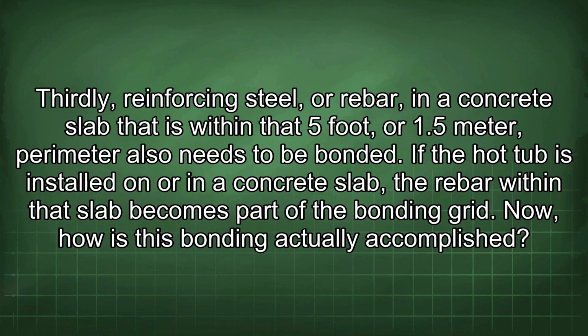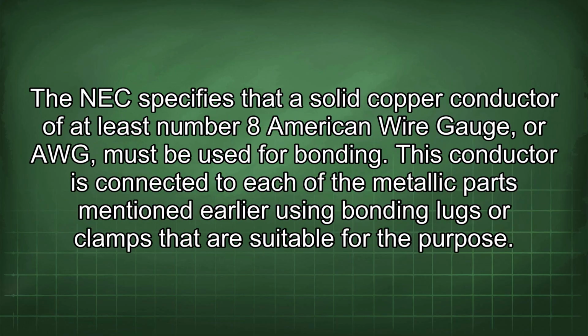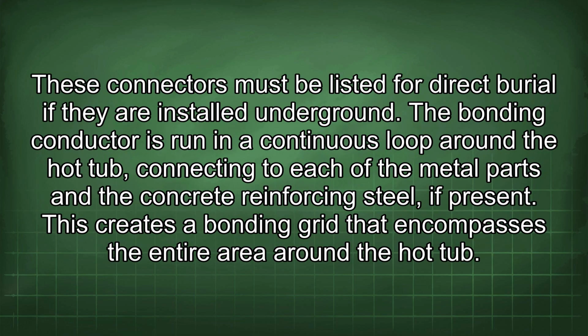Now, how is this bonding actually accomplished? The NEC specifies that a solid copper conductor of at least number 8 American wire gauge, or AWG, must be used for bonding. This conductor is connected to each of the metallic parts mentioned earlier using bonding lugs or clamps that are suitable for the purpose. These connectors must be listed for direct burial if they are installed underground. The bonding conductor is run in a continuous loop around the hot tub, connecting to each of the metal parts and the concrete reinforcing steel, if present. This creates a bonding grid that encompasses the entire area around the hot tub.